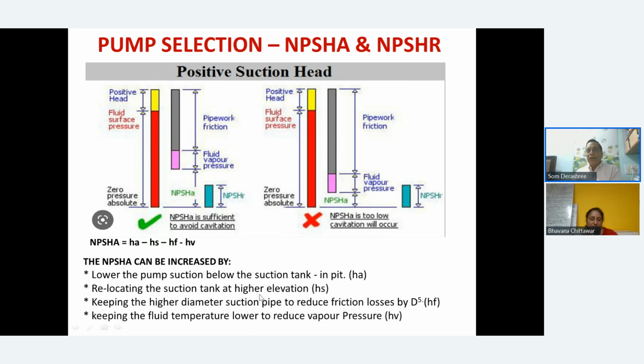Or if you cannot go into the pit with the pump, then you raise the tank height to the elevation from where the pump is sucking. Or keep a higher diameter suction pipe to reduce the friction losses. The friction losses are reduced by d to the power 5, so keep that in mind. Maybe have a little more liberal piping. And keep the fluid temperature lower to reduce the vapor pressure.